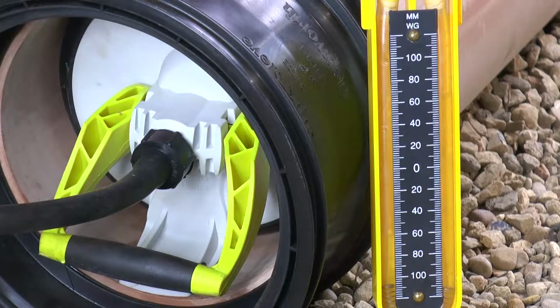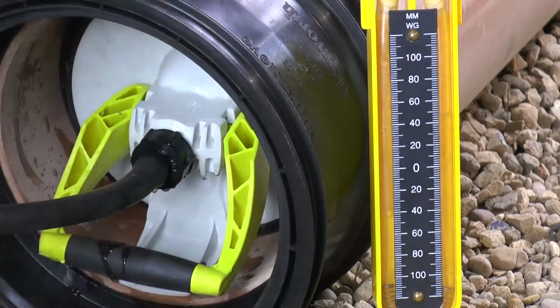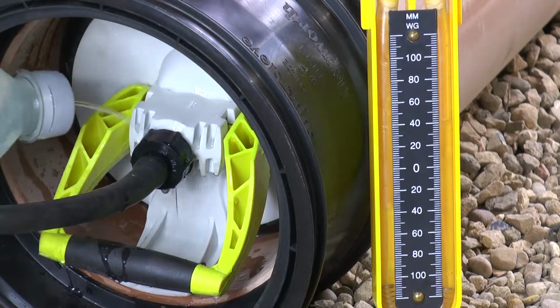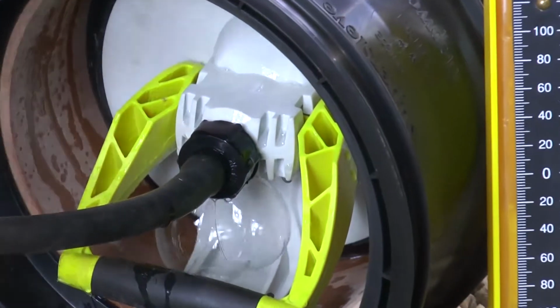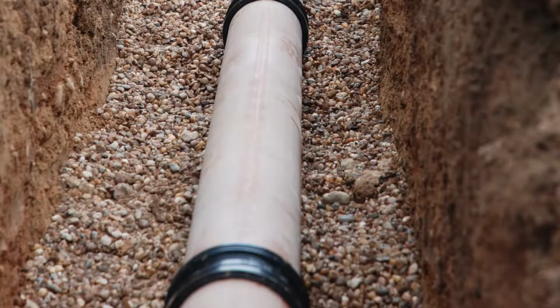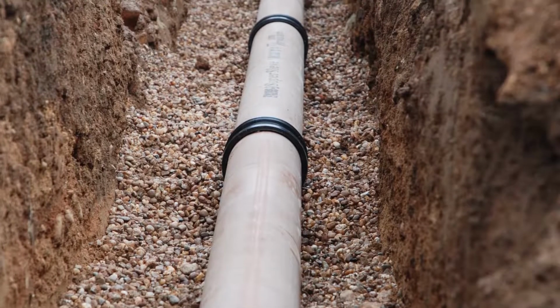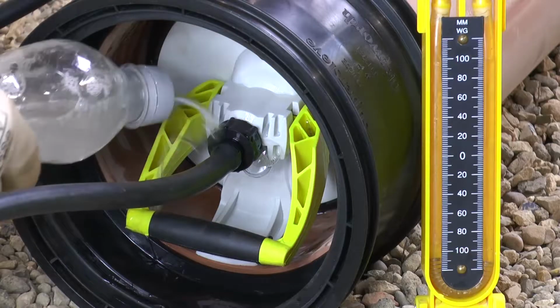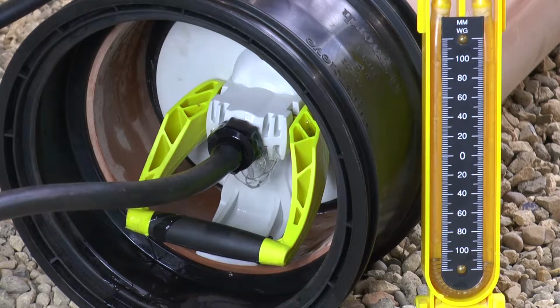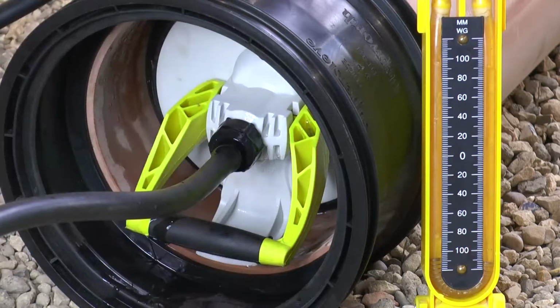Use dilute washing up liquid to identify any air leaks from the testing equipment by liberally coating all connections with the fluid and correcting any issues found. If you still can't get a test to hold, then visually check the pipeline to ensure that all of the joints have been made correctly, and by coating any suspect joints liberally with the fluid to check for leaks. Remember, the leak may be found anywhere on the seal contact area, typically where it's hard to see and locate.